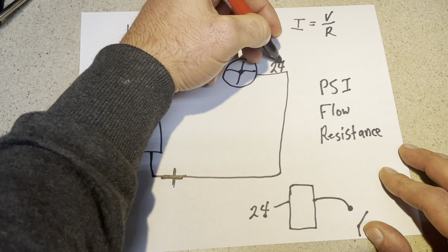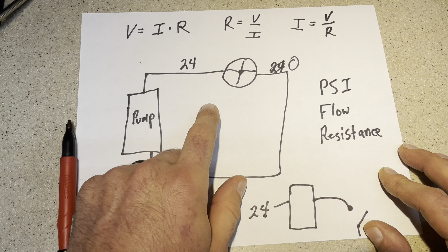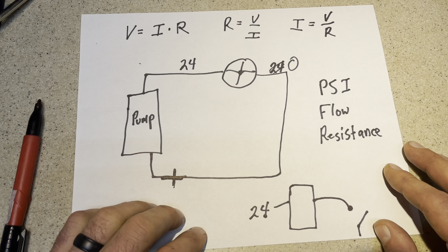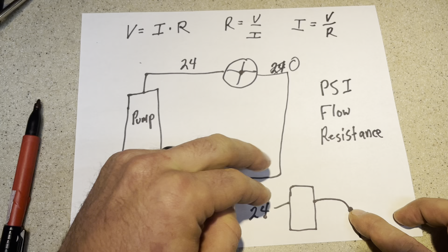And that's why if you measure across the contactor when it's on, you're going to see 24 volts. Because what the meter is telling you is that if the electrons had a way to jump around this, they would. So if you took a wire and hooked it here and went over here, they would say, nah, we don't want to go through this. This is too much work. Boom, we're just going to jump around it. And they want to jump around this 24 volts badly. You know what I'm saying? That's how bad they want to get around this resistance. So if I switch my contactor on and I measure, now I've got 24 volts at the contactor.